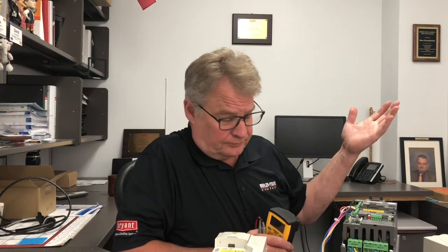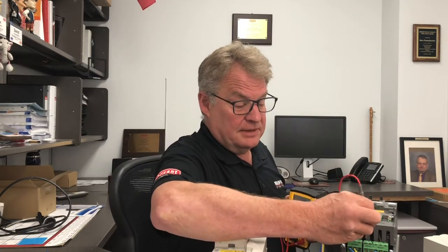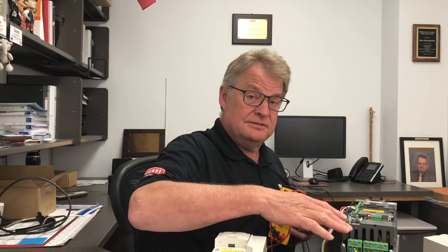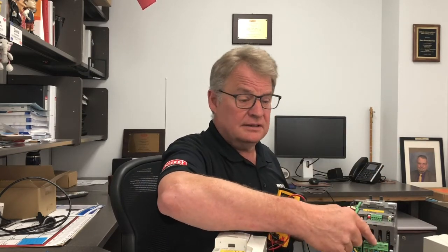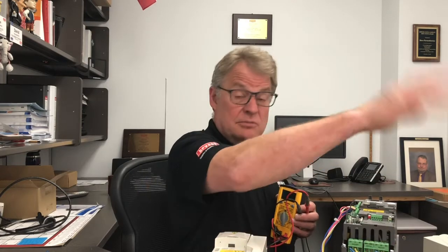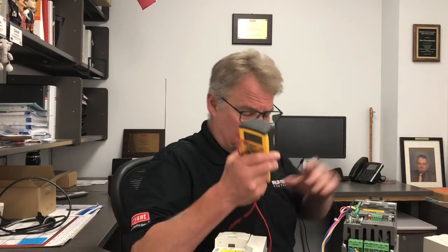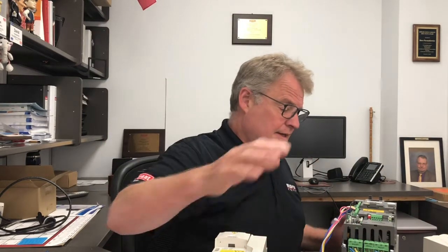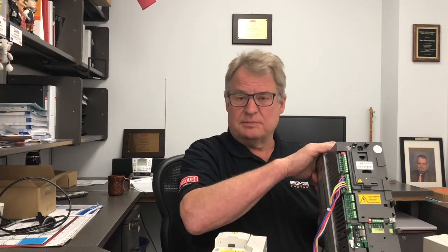All right. If I have line voltage coming out, now it might not be full 230 volts. Coming out of the drive, the voltage could be different, but if I have the same voltage on all 3 legs on the output, and the motor's not running, now we're going to look at the motor. So we're going to ohm the motor out, check the overload, whatever, we're going to check the motor side.